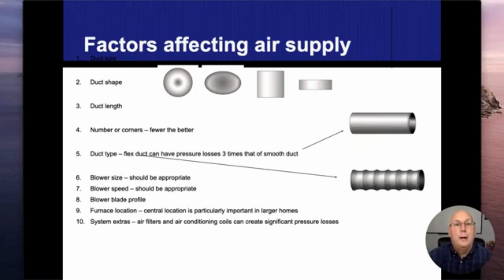So the shapes, the more round they are, the easier air is to flow. The distance and size of the ductwork matters. The smoothness inside. We find those corrugated loop ones sometimes in attics. It's not very common in the Chicago area, but it's getting to be more and more common. So the rougher they are, the bigger the chance to reduce the airflow, the bigger the pipes that they need to be. Hot air does move easier through ductwork than cold air. So not only do we have to size the ductwork for the heat, but we also have to size it for the air conditioning. Typically, most furnace fans, they're going to blow at a higher speed when it's running in air conditioning mode because we know cold air is harder to push through the ductwork. So the fan will make up that weakness that it needs.